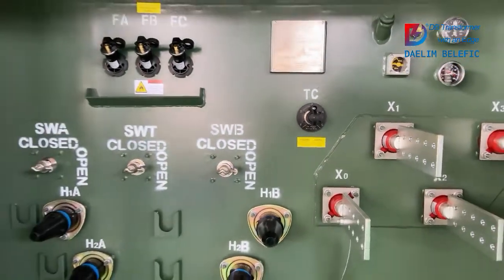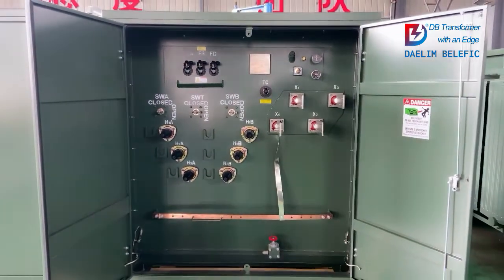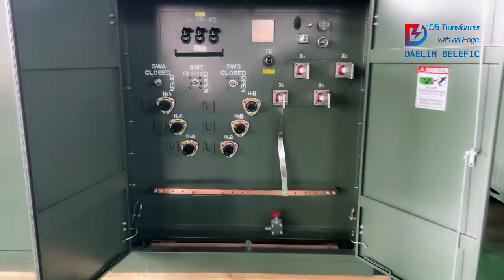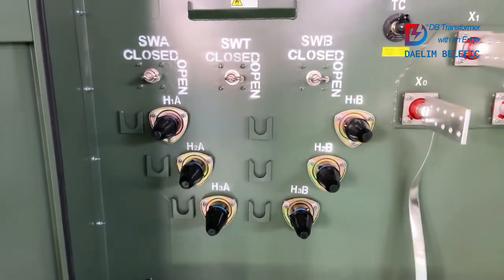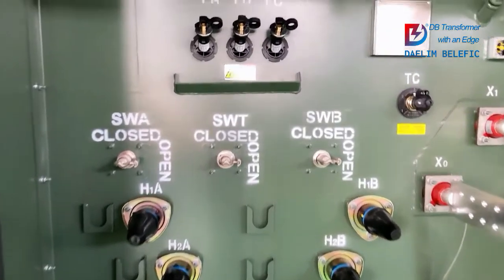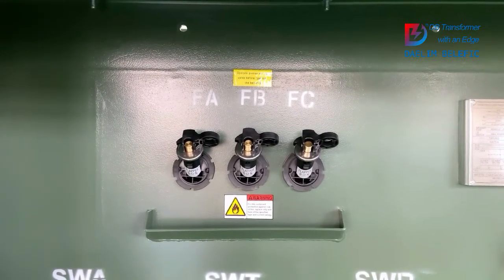Now we can have a better review of the whole unit. Loop feed design with 3 load break switches based on customer's requirements. On the left-hand side are the HA bushings, and the right-hand side are the HB bushings for high voltage. The 3 load break switches on the left are for HA, and on the right are for HB. Here are the bayonet fuses for the HB part protection.